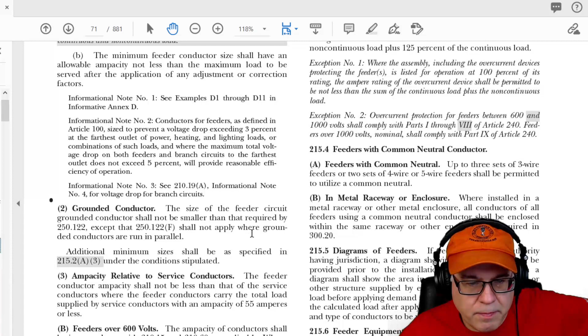Let's see here, it should be at the beginning. Yeah, okay, right here, so here it is on the screen. It says where a feeder supplies continuous loads and any combination of continuous and non-continuous loads, the minimum feeder conductor size shall be the allowable ampacity of not less than the non-continuous load plus 125% of the continuous load. That means a non-continuous load means 100% of whatever the load was, and 125% is for the continuous load. Okay, so that's where I got the requirements for that.